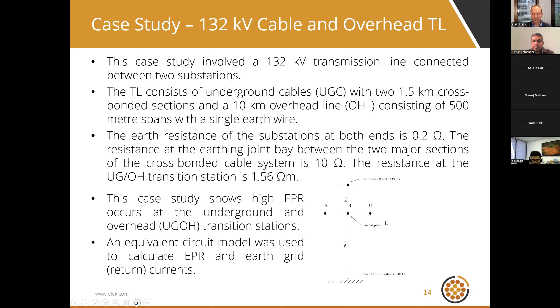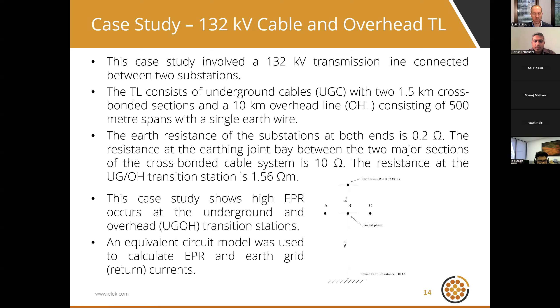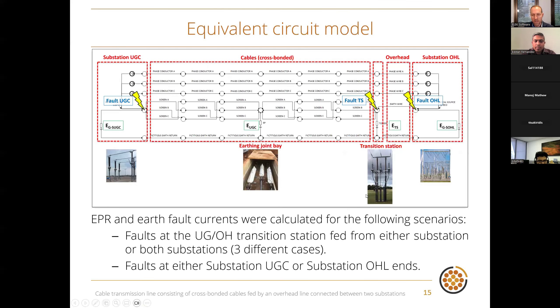The software schematic shows the system: in the middle is a 1.5-kilometre cross-bonded cable system, connected via a transition station to a 10-kilometre overhead line, with two substations at either end. The transition station is where the transmission line transfers from overhead to underground. On the left you can see cable sealing ends in the substation, and on the right there are gantries with an overhead transmission line termination.